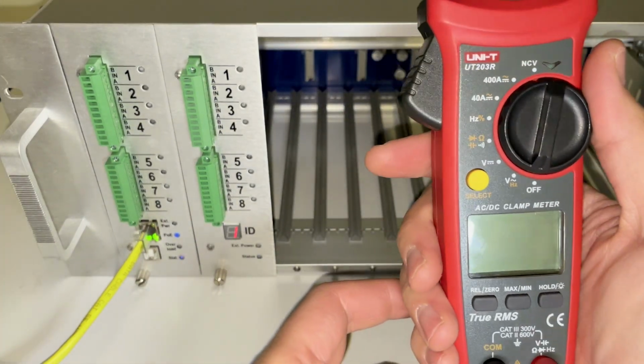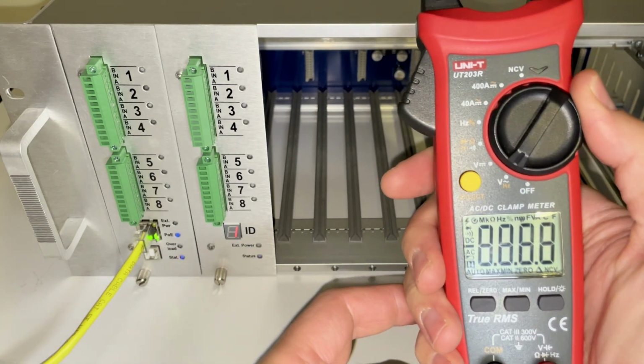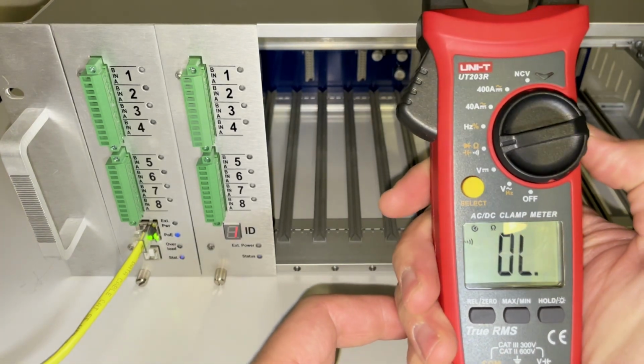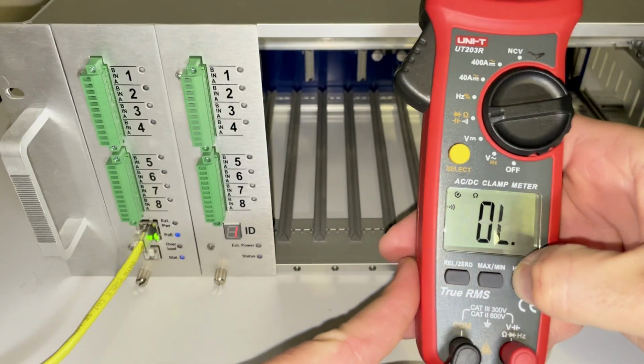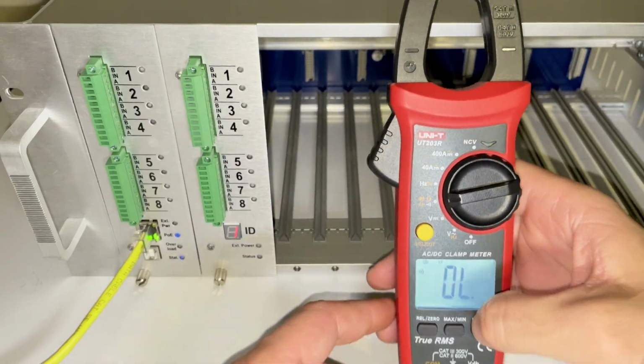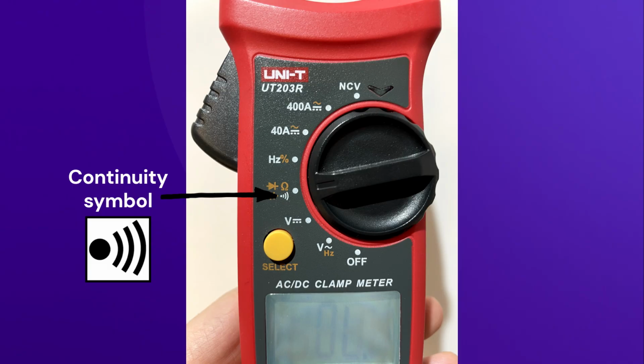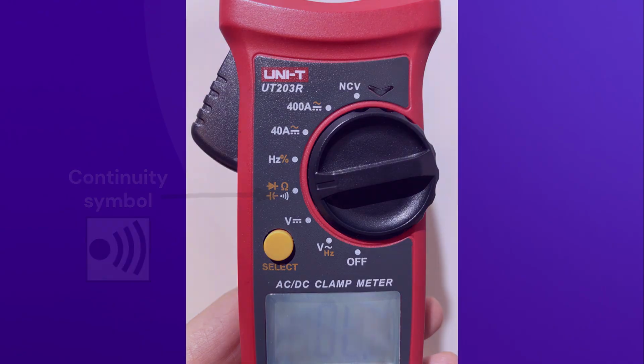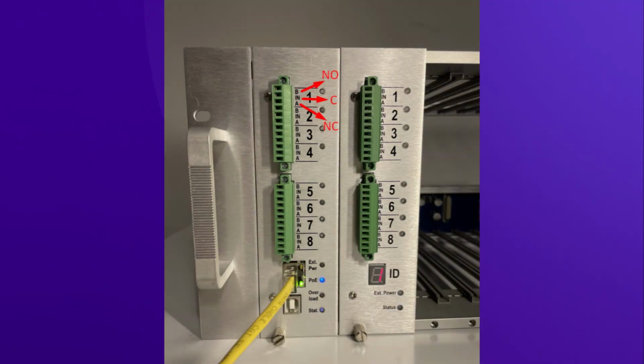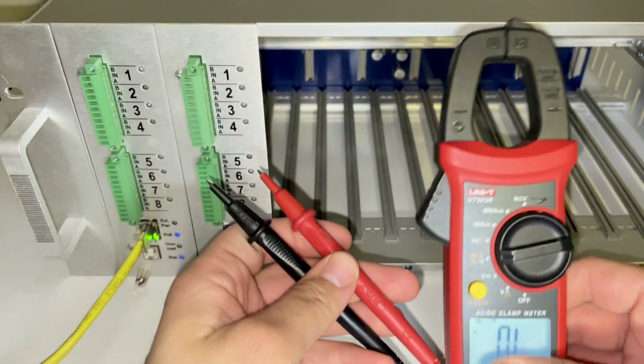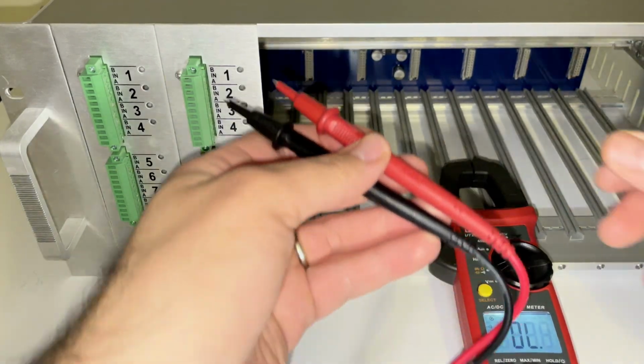To troubleshoot the dry relay, set the multimeter to continuity mode or resistance mode. Continuity mode is typically identified by a symbol resembling a Wi-Fi signal. The normally open contact is labeled with the letter B, the common contact is labeled IN, and the normally closed contact is labeled A. Begin by testing the normally open contact.